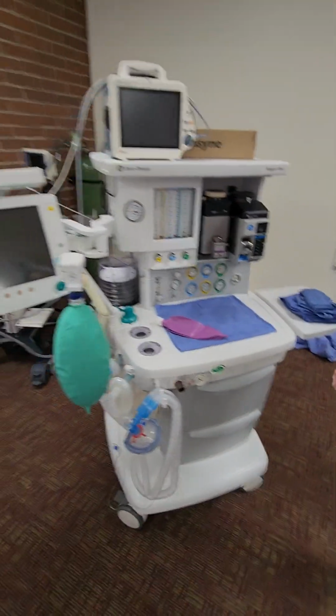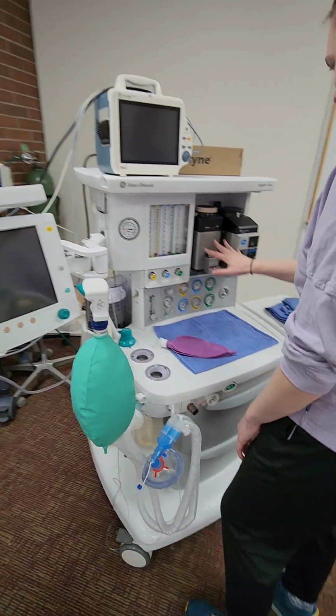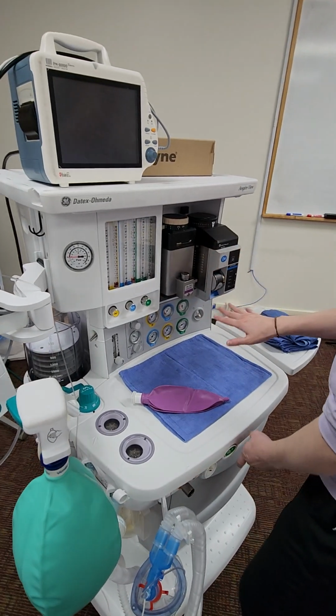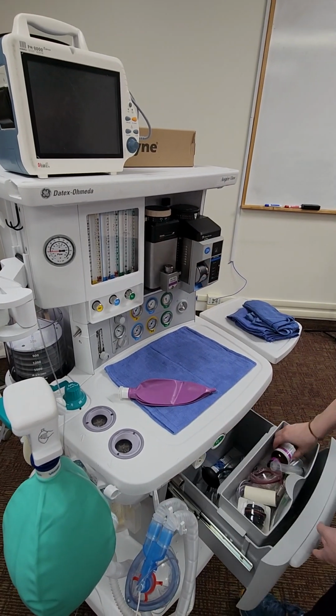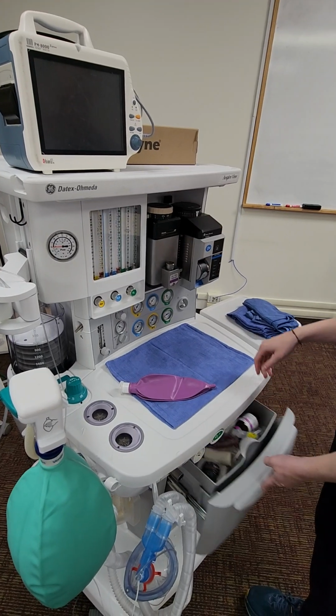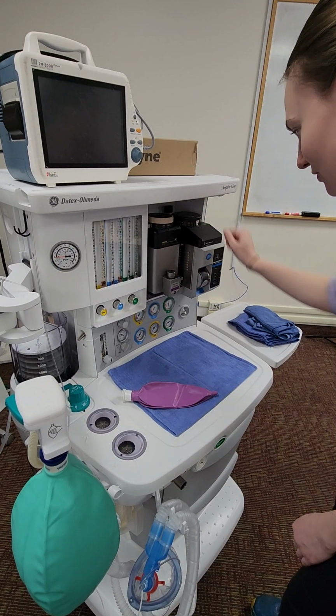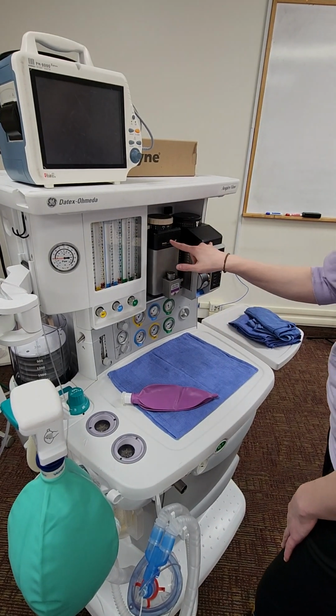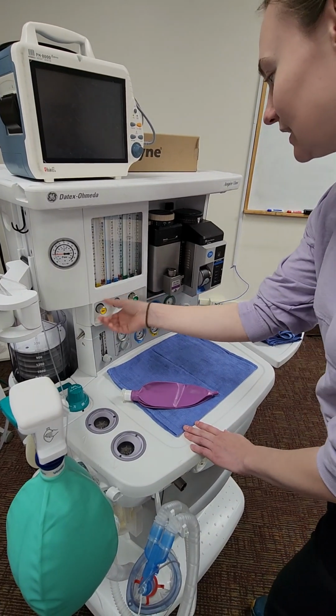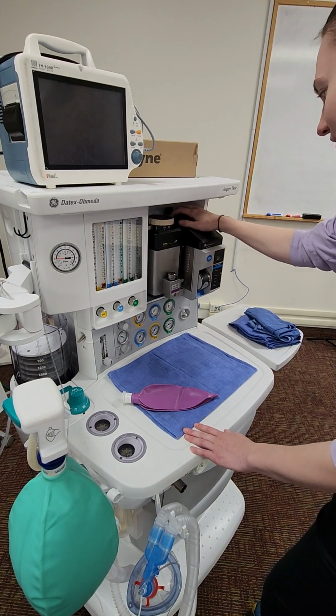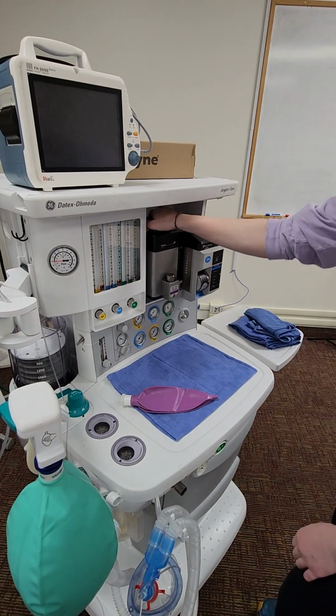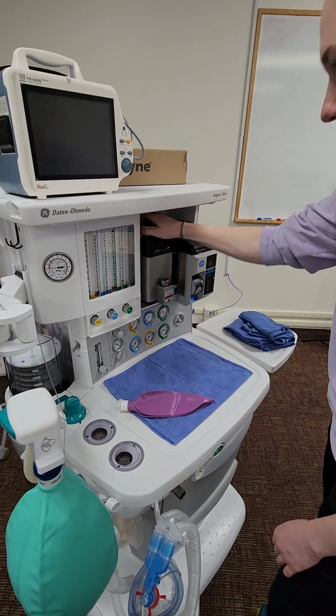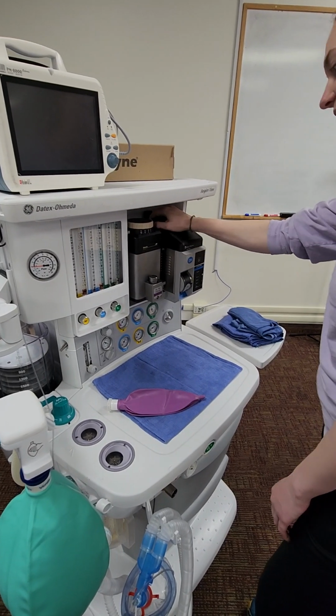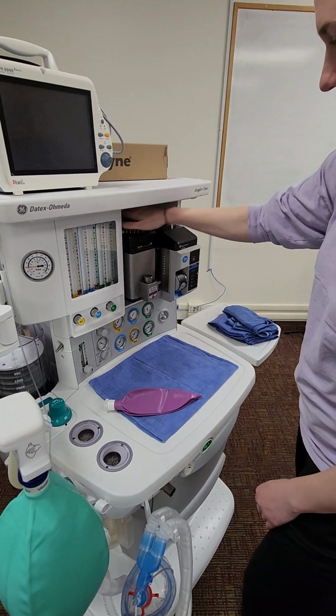So now you'll come to the front. You'll do a little inspection. You want to make sure your DES is completely, like you have enough anesthetic gas. If not, you can fill it up. You just want to make sure you rescrew these caps when you refill these things, your vaporizers. You'll make sure these are all securely closed. And you can also verify your interlock system. So you'll turn one on. You can make sure you can't turn two vaporizers on at one time.